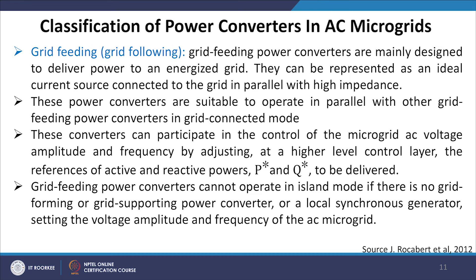Let us consider the classification of power converters in AC microgrids, starting with grid feeding or grid following. Grid feeding power converters are mainly designed to deliver power to an energized grid. They can be represented as an ideal current source connected to the grid in parallel with a high impedance. These converters are suitable to operate in parallel with other grid feeding power converters in grid-connected mode. They can participate in the control of the microgrid AC voltage amplitude and frequency by adjusting, at a higher level control layer, the reference of the active and reactive power P and Q to be delivered.